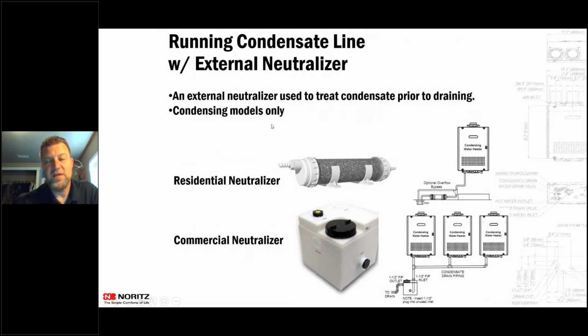Any questions on the condensating side? The neutralizer, is that code here in Utah, or is that just something that's out of state? I've never heard of that before. What are the rules here for that? It's not code in Utah that you have to neutralize the condensate going out. I just want to make everybody aware that it is available. In some places, it depends on the job. I've seen some jobs on commercial sites where they require it through the spec. When the engineer's speccing it out, they'll throw neutralizers in, but normal install, residential, commercial, it's not required that you neutralize that condensate.